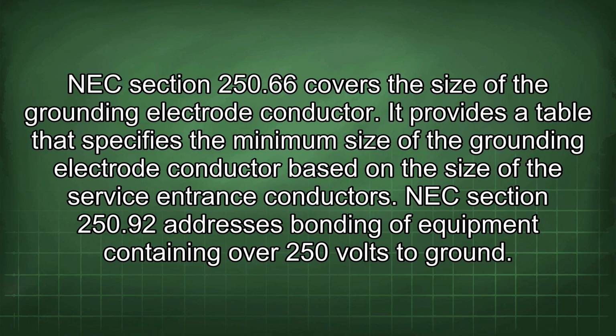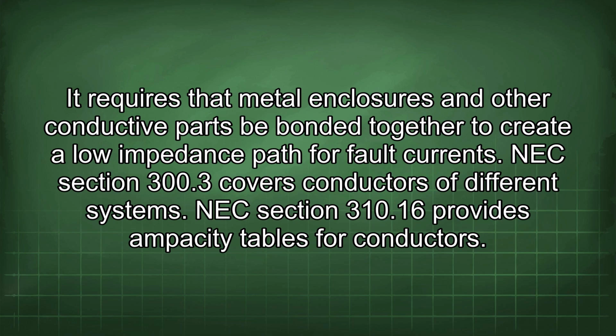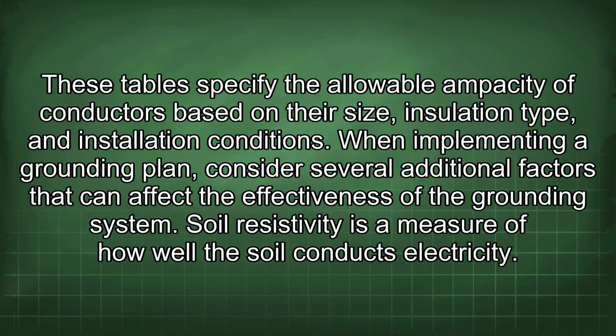NEC Section 250.66 covers the size of the grounding electrode conductor. It provides a table that specifies the minimum size of the grounding electrode conductor based on the size of the service entrance conductors. NEC Section 250.92 addresses bonding of equipment containing over 250 volts to ground. It requires that metal enclosures and other conductive parts be bonded together to create a low impedance path for fault currents. NEC Section 300.3 covers conductors of different systems. NEC Section 310.16 provides ampacity tables for conductors. These tables specify the allowable ampacity of conductors based on their size, insulation type, and installation conditions.